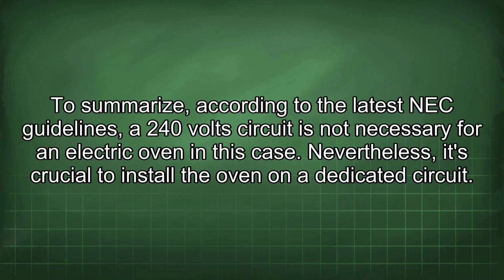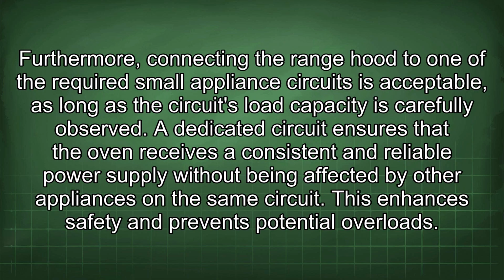To summarize, according to the latest NEC guidelines, a 240-volt circuit is not necessary for an electric oven in this case. Nevertheless, it's crucial to install the oven on a dedicated circuit. Furthermore, connecting the range hood to one of the required small appliance circuits is acceptable, as long as the circuit's load capacity is carefully observed. A dedicated circuit ensures that the oven receives a consistent and reliable power supply without being affected by other appliances in the same circuit. This enhances safety and prevents potential overloads.